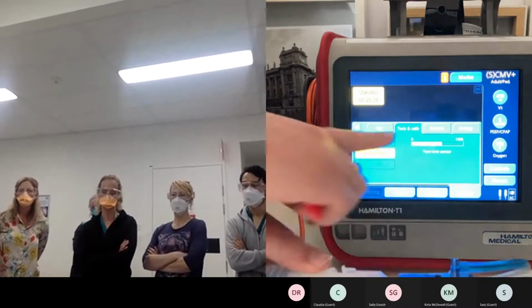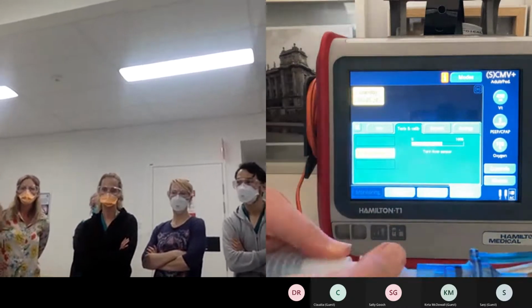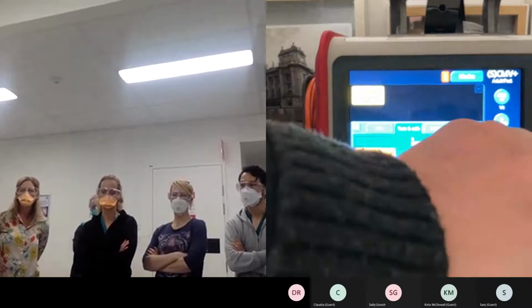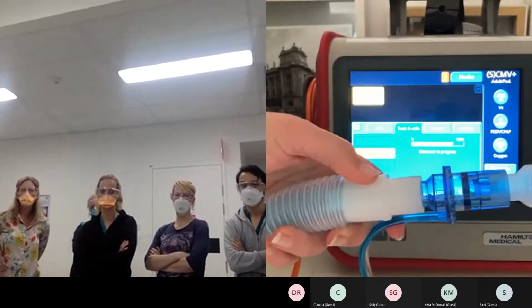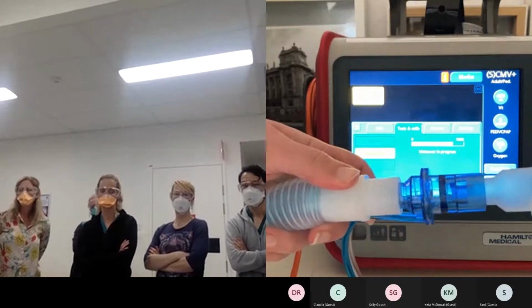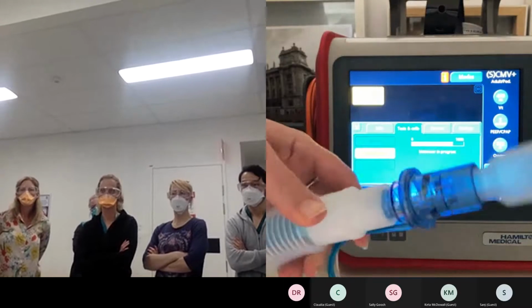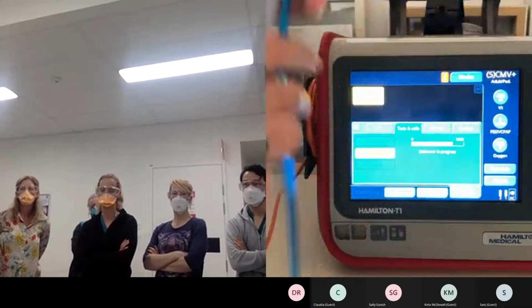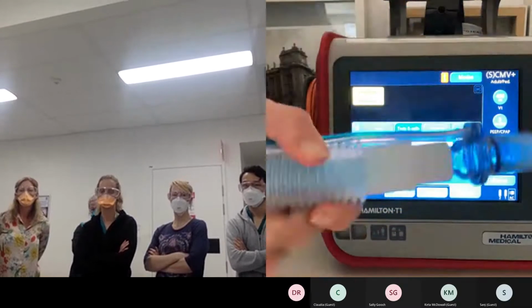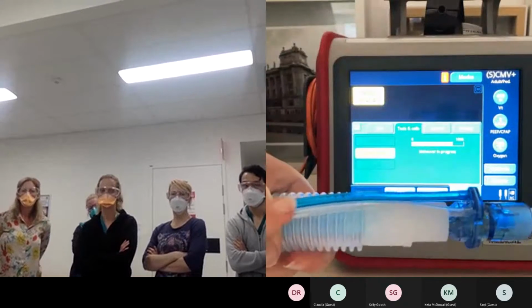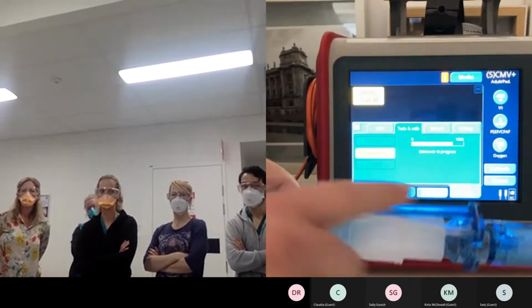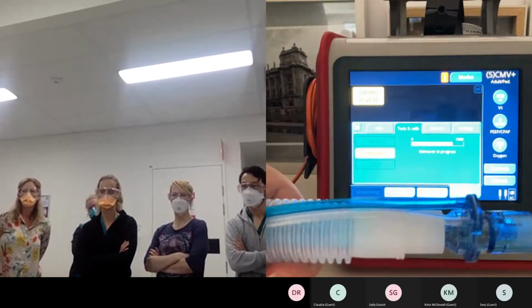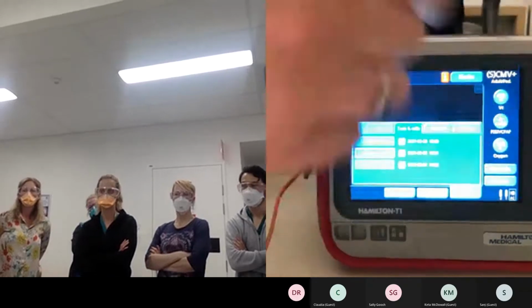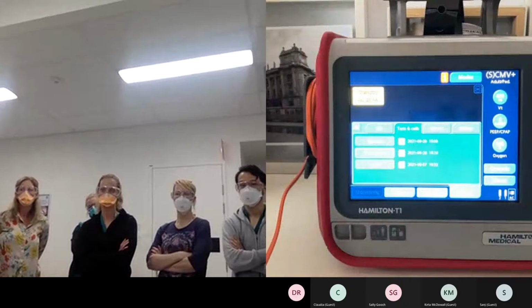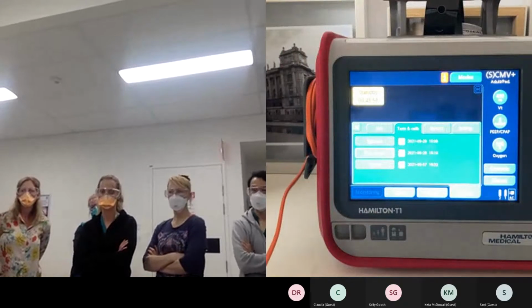Okay, so you can hear it building. Now it says turn flow sensor. So you take it out and you pop it back. Okay, so it ends back in the position that it will go onto the patient. The reason that you have to turn it is because it's almost zeroing itself at each of those points, so that when it's on the patient, it's able to measure what's going in and what's coming out. Okay. And again, you get a green tick, date and time of completion.